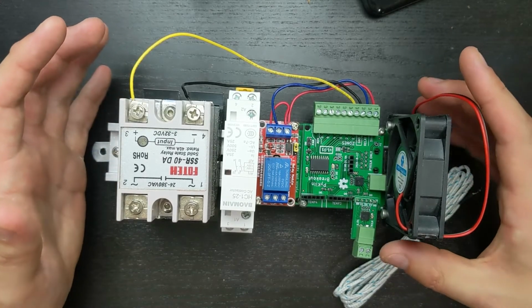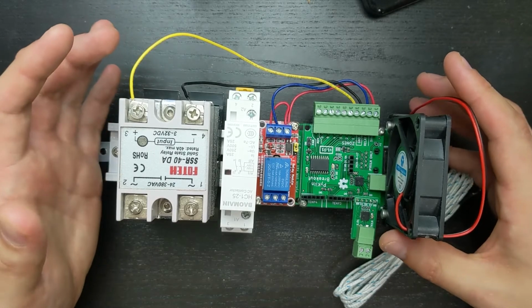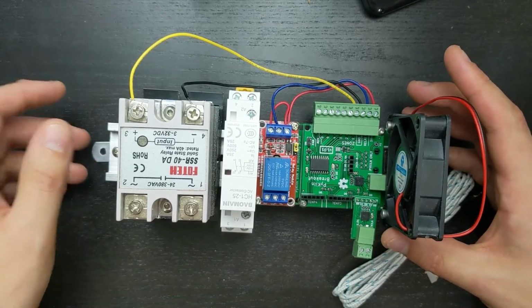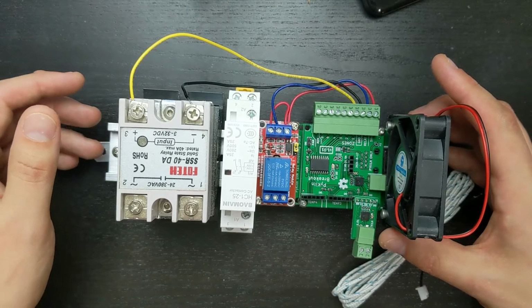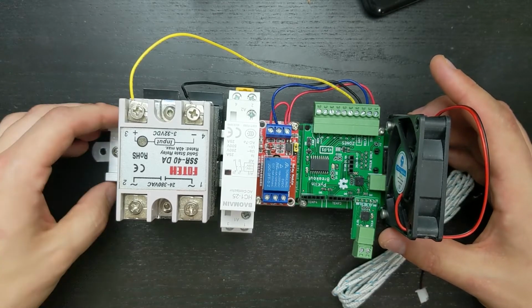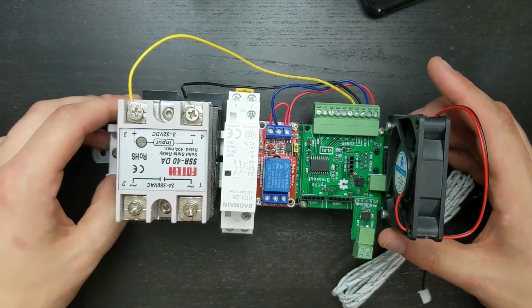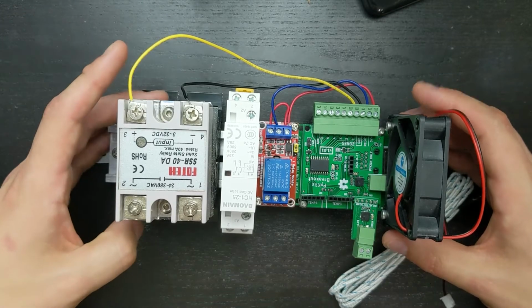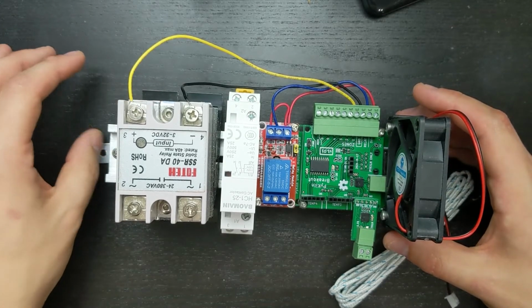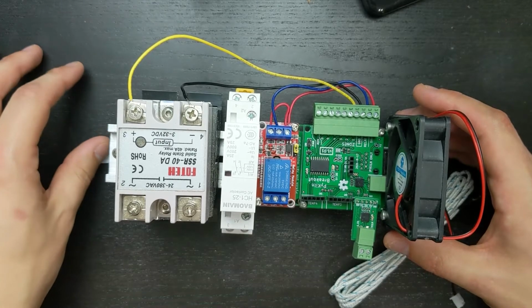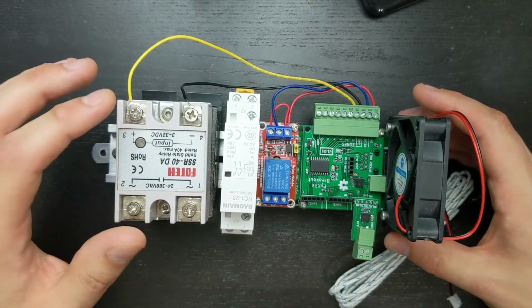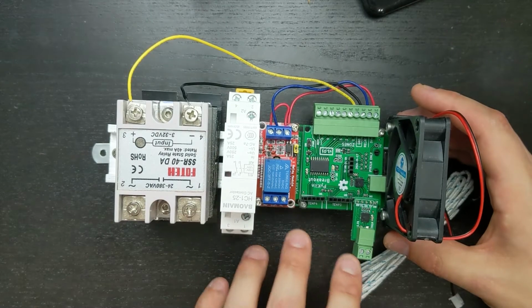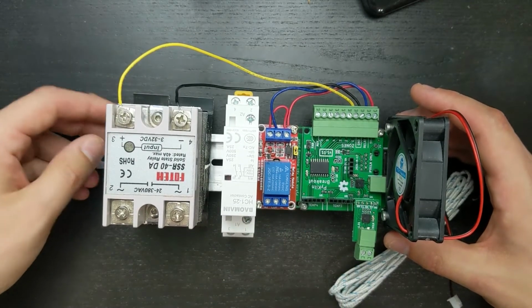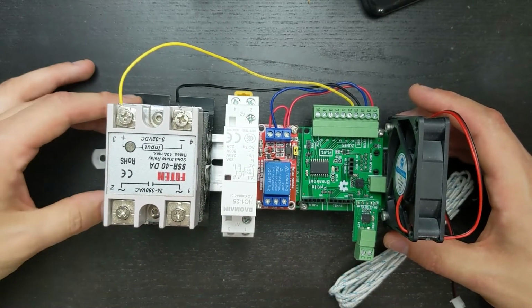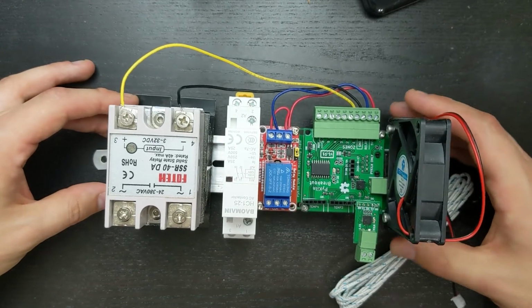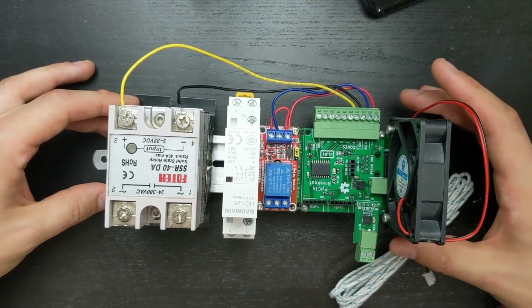Along with heat, I actually had Corey do some tests with his kiln and some DIN rail and offset clips. And he found that the outside of his kiln on the DIN rail was getting up to about 140 degrees Fahrenheit, which is definitely a lot cooler than the surface of his kiln, but it's still a little bit too warm for my liking, especially considering we have all these plastic components. I just don't want them to deform and melt over time. So by adding a fan, it's definitely going to keep things a lot cooler.